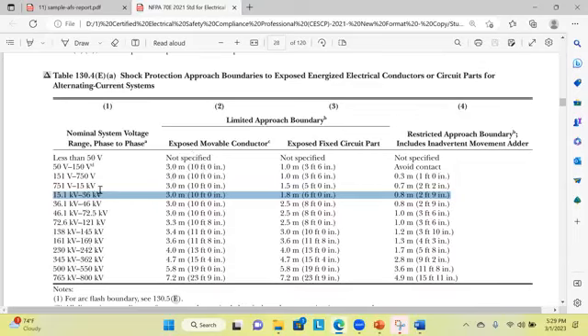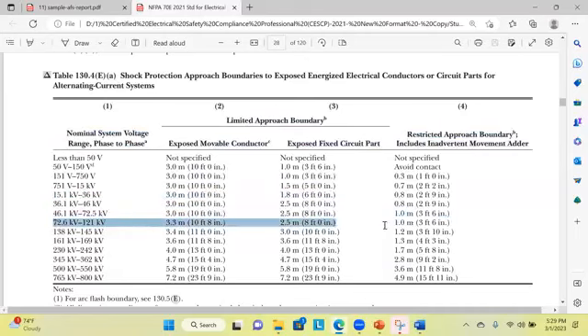Another example is if the voltage does not fall in this table, for example 132 kV. They ask you about 132 kV. Here it is 121 kV and here it is 138 kV. So we jump to the higher one and assign the distances related to the higher voltage level. This row is from 72 kV to 121 kV, and this row is from 138 kV to 145 kV. So in this case we look at the higher voltage level. If it is an overhead line, the limited approach boundary will be 11 feet and the restricted approach boundary will be 3 feet. On the other hand, for the fixed conductor, the limited approach boundary will be 10 feet and the restricted approach boundary remains the same.